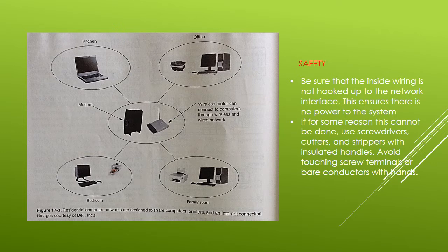Keep the telephone and network wiring at least 2 feet away from power circuits in the building. To avoid high voltage shock, keep telephone cable pairs away from accidental contact with 120 or 240 line current. Never remove protectors or grounding means placed by the telephone company. Do not modify these installations to make any connection to them.